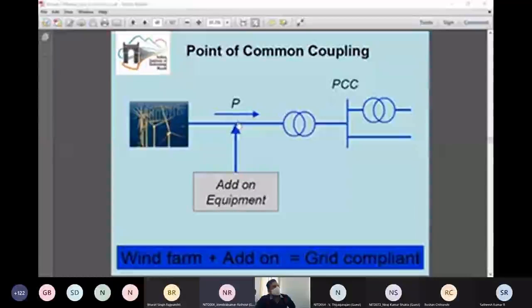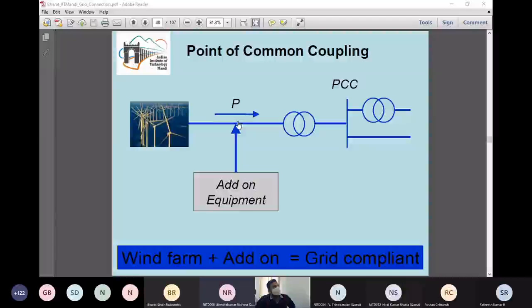Hello, good morning, sir. Yes. Sir, I'm a bit confused with one point. You have shown the percentage of power available and the frequency matching diagram. So suppose the grid frequency is between 50 to 51 hertz. So at that moment, the power available from the wind power is between 15 to 100%. Okay, so that curve that you are talking about is of active power requirement.